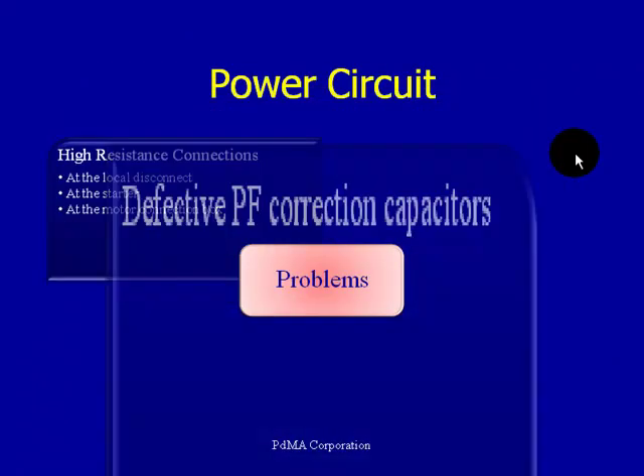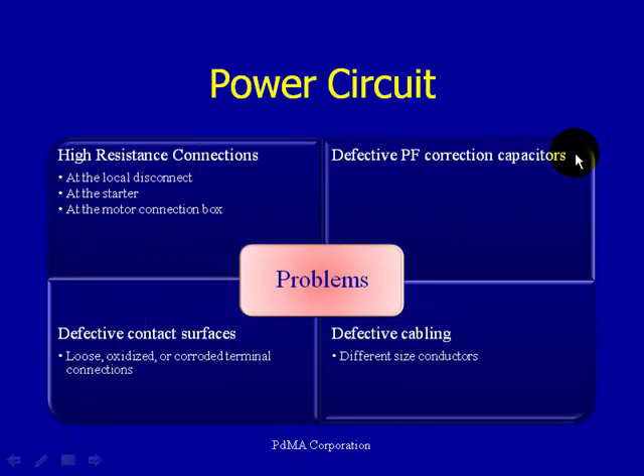What are some of the problems in the power circuit? High resistance connections are one — at the local disconnect, at the starter, or at the motor connection box. A high resistance connection on one of those phases can result in an inefficient running motor. Other issues include defective power factor correction capacitors, defective contact surfaces, oxidation, loose connections — all of which contribute to high resistive imbalances — as well as defective cabling and different size conductors.